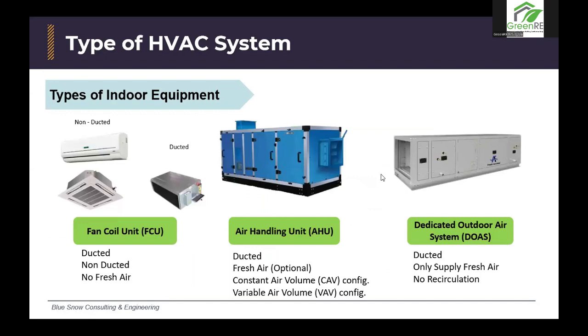The next, okay, this is the types of indoor equipment. We have four types. The first one is the fan coil unit, also known as the FCU. Usually this one has two options, ducted and not ducted, and there is no fresh air supplied to this unit. The second one is the air handling unit. It's ducted, and there's an option for the AHU to supply fresh air or not. There are two options, which are constant air volume configuration and also variable air volume configuration. The last one is the dedicated outdoor air system, or DOAS. This one is also ducted and only supplies fresh air from the outside, with no recirculation.